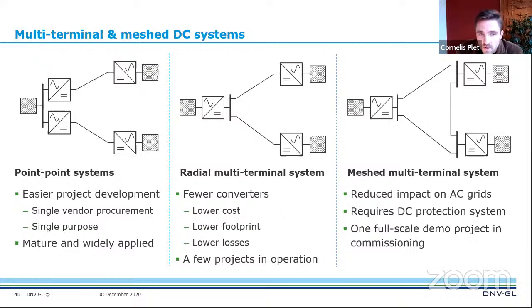The only problem is that in case of a DC fault, there's no redundant path. That's problematic for large HVDC system ratings when you go into the multi-gigawatt range, because we might exceed the maximum loss of infeed in the AC synchronous area it's connected to. One solution to this could be the meshed multi-terminal system, shown on the right.